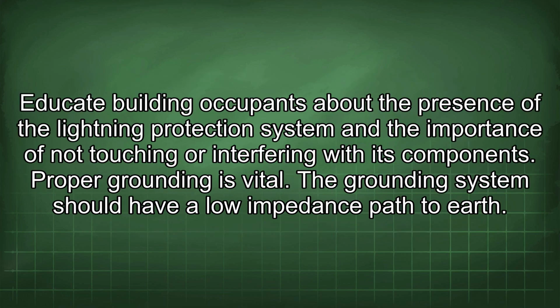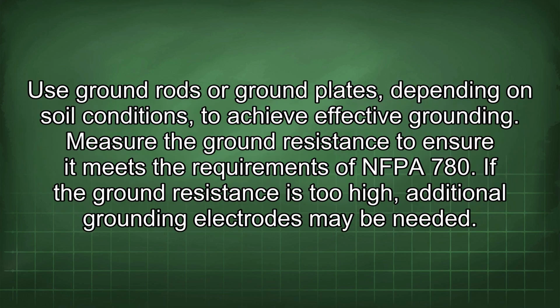Educate building occupants about the presence of the lightning protection system and the importance of not touching or interfering with its components. Proper grounding is vital. The grounding system should have a low impedance path to earth. Use ground rods or ground plates, depending on soil conditions, to achieve effective grounding. Measure the ground resistance to ensure it meets the requirements of NFPA 780. If the ground resistance is too high, additional grounding electrodes may be needed.